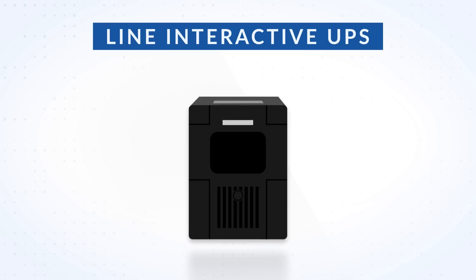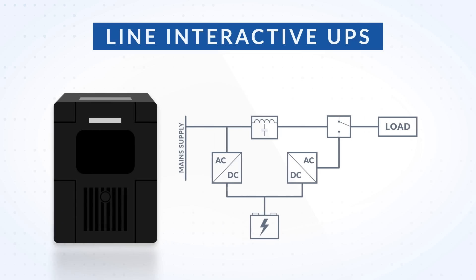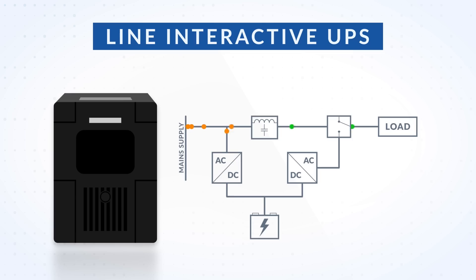The Line Interactive UPS is a modification of the Offline UPS. It has an automatic voltage regulator that senses fluctuations and stabilizes the output power. As a result, battery life is prolonged and the power that goes to the load is processed. If the mains power is too low, then it switches to the batteries.